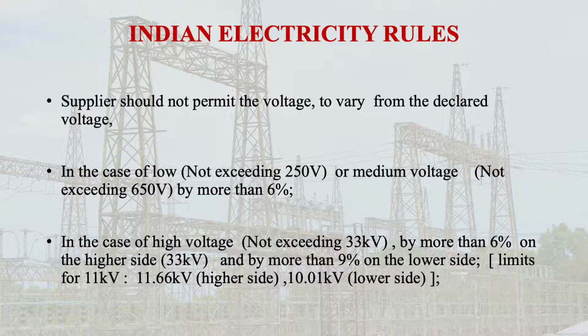as per these rules. Then in case of high voltage, by more than 6% on the higher side and more than 9% on the lower side. High voltage means not exceeding 33 kV. So in the case of this high voltage, the higher side allowed is only 6%. This is the limit. It should not vary more than this. And the lower side, that means the minus side, should not be more than 9%.